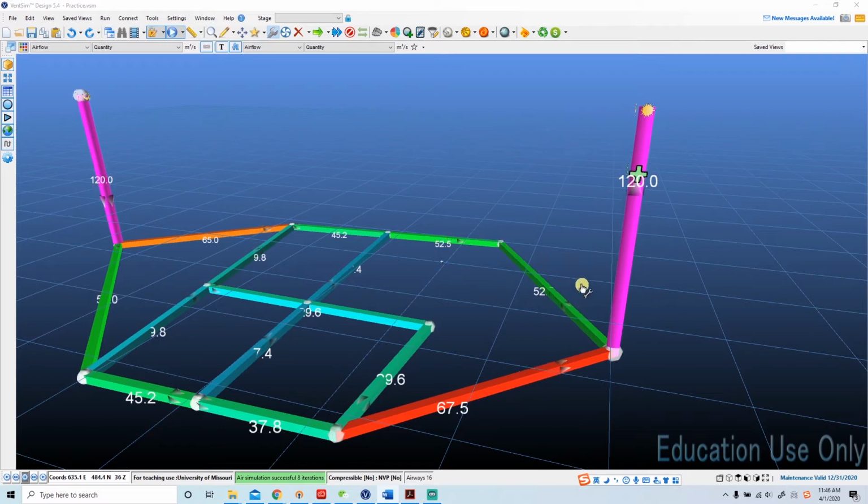If you need 80 cubic meter per second in the top branch without changing the total airflow quantity to the mine, we can put a regulator in the lower airway and restrict airflow in it, so more air will be pushed to the top airway. So if we regulate the airflow in the lower branch down to 40, then there will be 80 pushing to the top branch. Basically, we can partially block the lower airway to cause congestion in it, so air will not move easily in the lower airway and more air will be forced to move to the top airway.